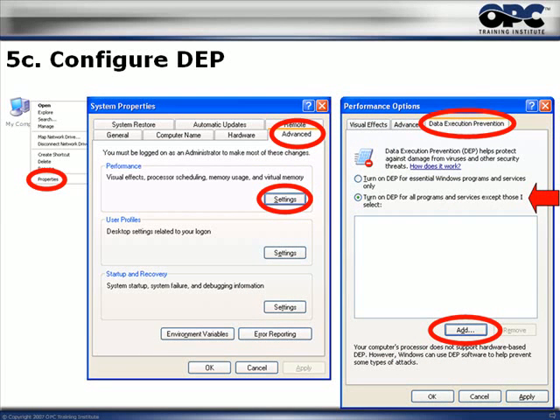Here, you'll need to add the affected OPC servers. Only add an OPC server if it's actually affected by data execution prevention — if it is, go ahead and add it. If it's not being affected, you don't need to worry about it. Click the Add button, and once you've added the OPC servers, clients, or whatever applications you need, click OK. You're done configuring data execution prevention, and you're also done securing your Windows operating system again.